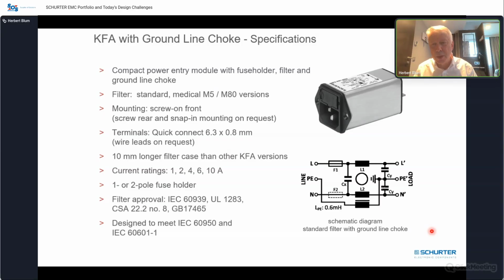This is another power entry module with integrated ground choke, with 2 fuse holders, especially for medical applications, because in medical applications they like or need to have double pole fuse holders. And they use this ground choke to get rid of ground loops. For example, think about patient monitoring systems where you have several devices connected together and connected to a patient - it can be a real problem with ground loops.